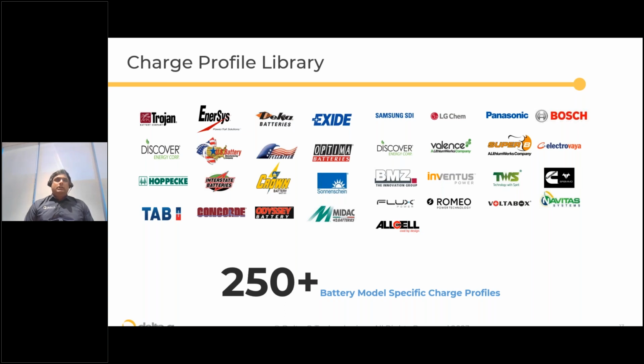For example, a lead acid battery has to be charged more compared to a lithium-ion battery, and even under lead acid, a flooded lead acid has to be charged more compared to a sealed lead acid. So if we use an algorithm designed for a flooded lead acid on a lithium-ion battery, we would overcharge and damage that battery.